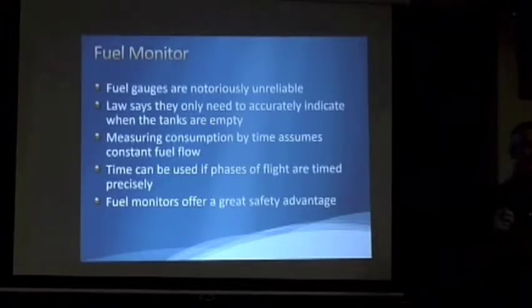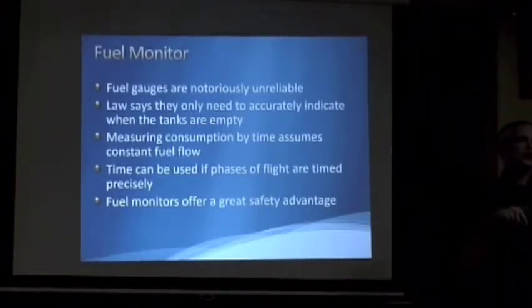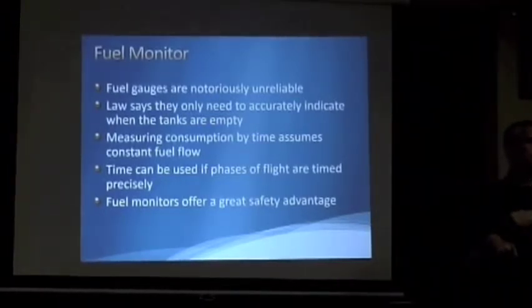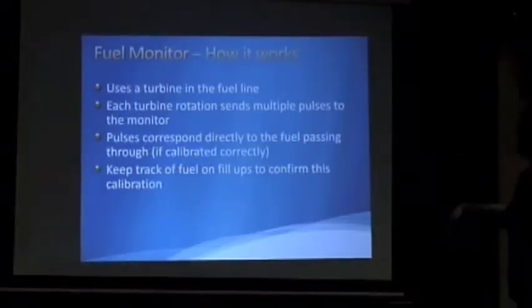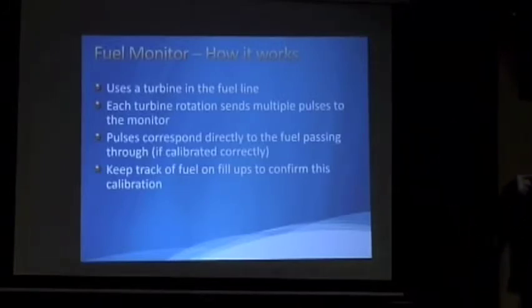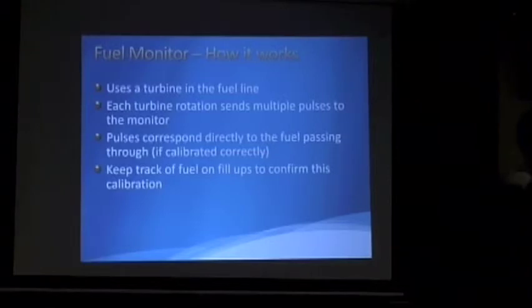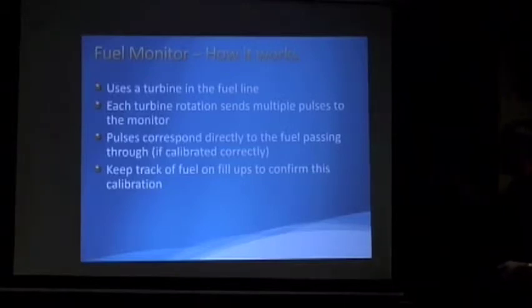Yep, and it has to be installed in such a way that it accounts for the return. A return fuel system? Yeah, it has to use a turbine in the fuel line. Basically, it's just like a little turbocharger spinning around inside, and each time it goes around it produces a pulse, like a Hall sensor or optical sensor idea, and the multiple pulses then indicate to the instrument how much fuel is actually going through it. More fuel moves through, the faster the turbine goes.